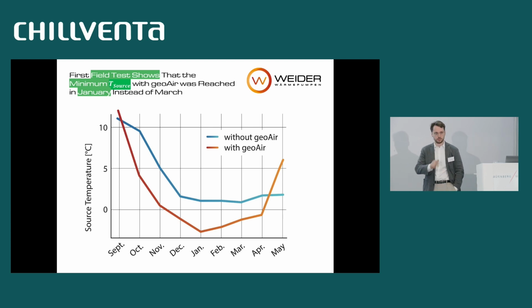And we compare two data lines here. The first one is the source temperature, which you can see in orange with the geoAir. You can see that the source temperature actually reaches its minimum in January, right? So after January, the geoAir puts more energy into the ground than it takes out, and we have an active regeneration from January. And usually the minimum source temperature is reached after winter, in March, April, and then it goes up when the heating stops. And the blue line is also from the same building. It's actually the cold water temperature, which shows that the minimum of the natural source without regeneration is actually reached in March and rises in April.